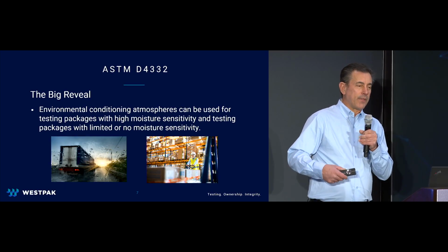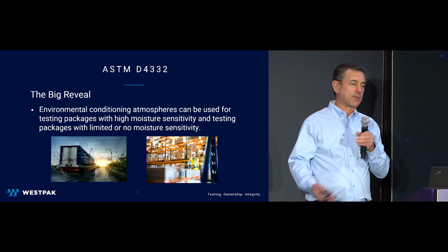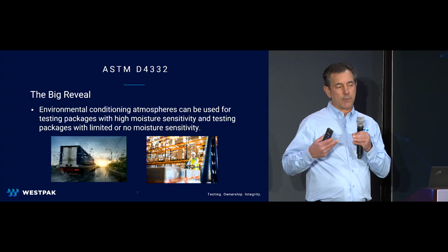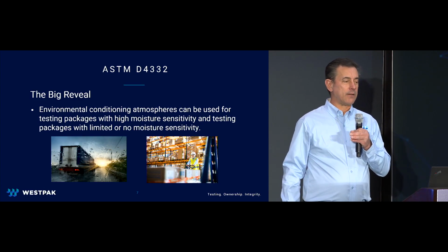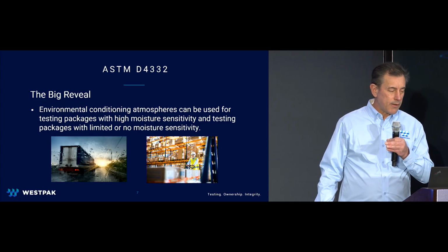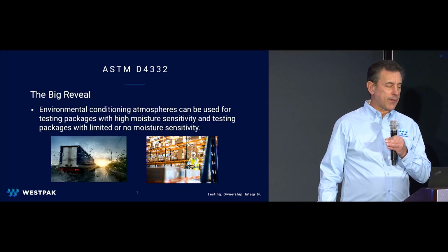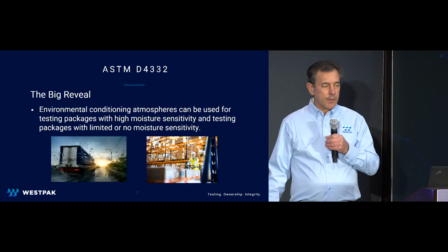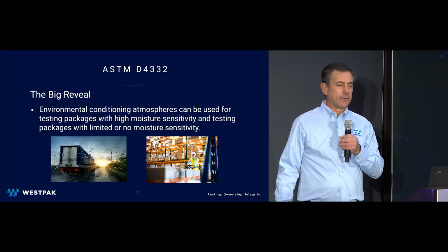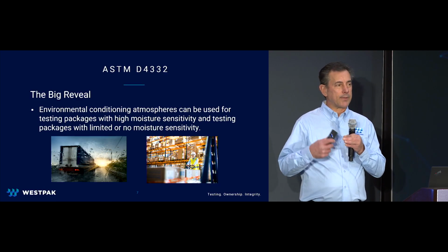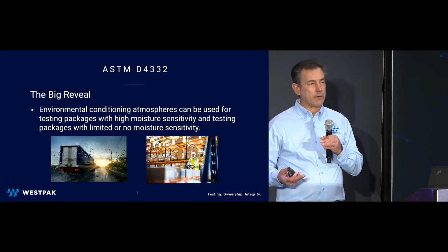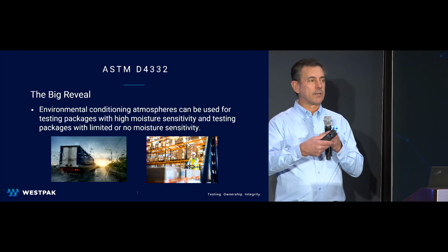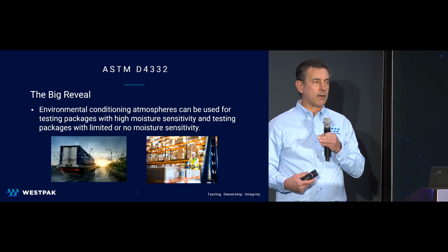So this is an attempt to bring in the consideration of moisture that we'll see later on in another standard, the accelerated aging standard. And this brings moisture to the forefront. Now, we've always had that. And ultimately, in the conditioning standard, you're supposed to know your environment. All of these standards say, know your environment.